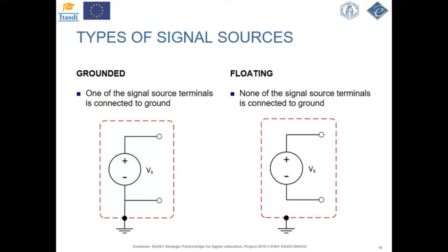On this slide, we can see the measurement of a grounded signal source with a ground referenced measurement approach. It is known that a grounded signal source is best measured with a differential measurement system. On this illustration, we can see the disadvantages of using a ground referenced measurement system to measure a grounded signal source. In this case, the measured voltage, Vm, is the sum of the signal voltage, noted here as Vs, and the potential difference, delta Vg, between the signal source ground and the measurement system ground. So this is Vg.